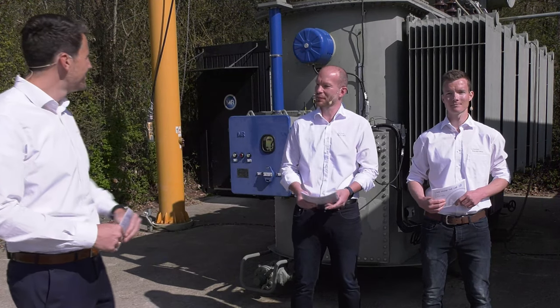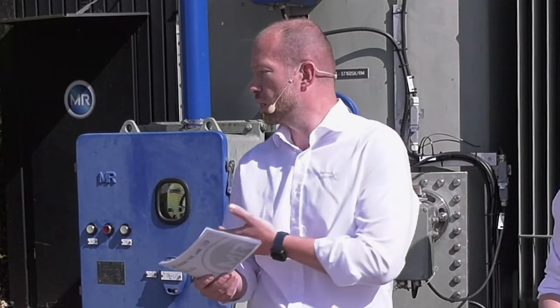So, Herbert. Thank you, Stefan, for the warm welcome. In the next couple of minutes, we would like to talk about technical specification, offer and order procedure, and hopefully in the end, the organization and preparation of the service at site. But first, why a motor drive unit may become necessary to replace. The root cause could be different. It could be that a component is damaged and no spare part is available. It could be a refurbishment of the transformer after 20 to 30 years, or maybe modernization and digitalization of the substation, which has become more and more frequent during the last months.